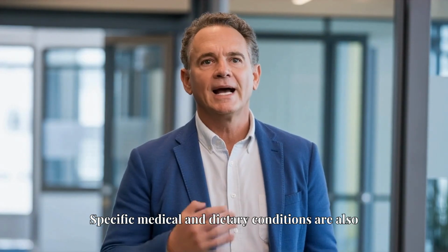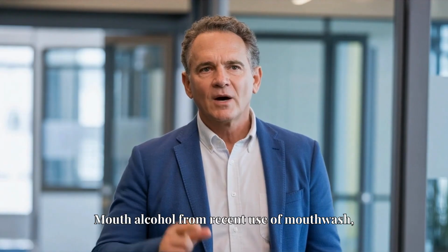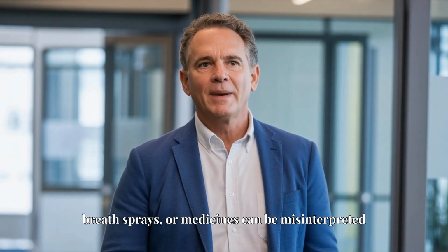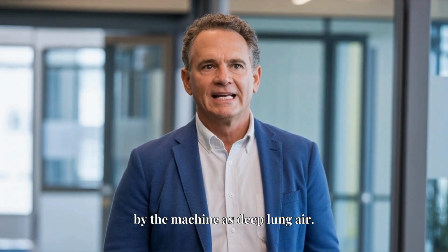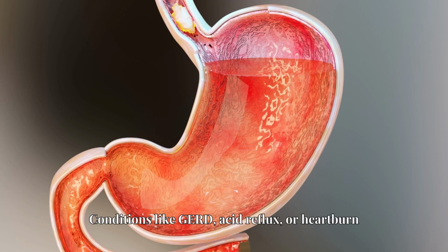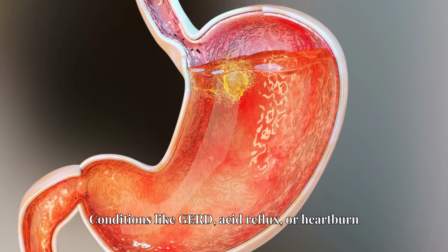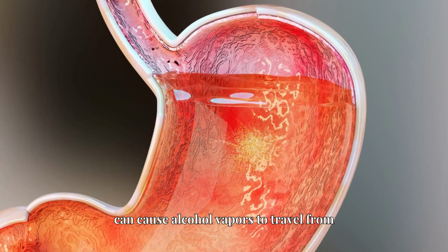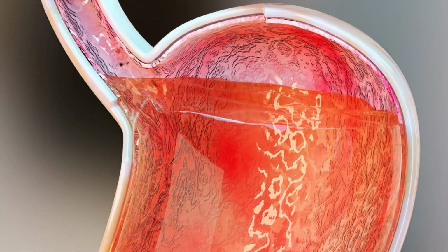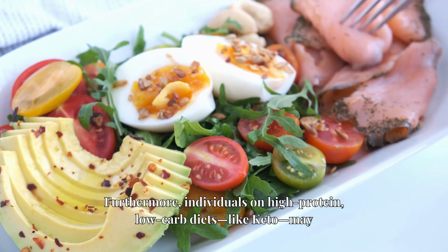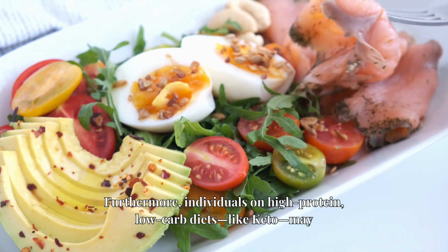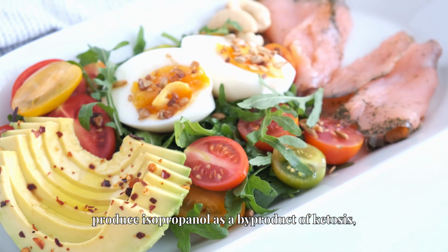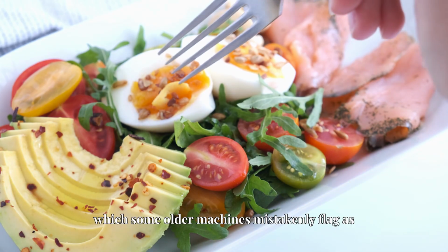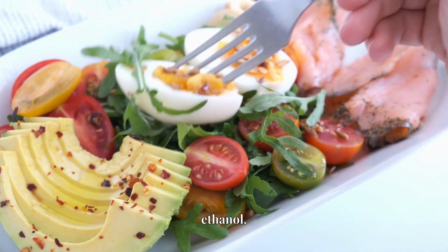Specific medical and dietary conditions are also known culprits. Mouth alcohol, from recent use of mouthwash, breath sprays, or medicines can be misinterpreted by the machine as deep lung air. Conditions like GERD, acid reflux, or heartburn can cause alcohol vapors to travel from the stomach back into the mouth. Furthermore, individuals on high-protein, low-carb diets like keto may produce isopropanol as a byproduct of ketosis, which some older machines mistakenly flag as ethanol.